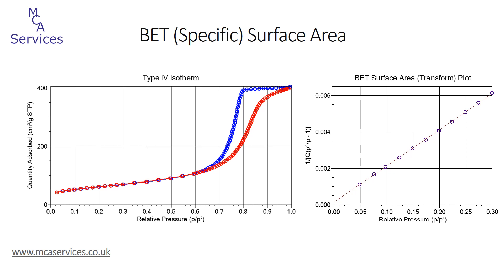There are several pieces of information that we can readily gain from this isotherm, and we're going to start by looking at the lower relative pressure portion of the adsorption isotherm. From this we can calculate the BET surface area of the material. We're going to cover this in much more detail in another video, but we can see the BET transform plot on the right, and the relative pressure range applied to it is 0.05 to 0.30. This provides a BET transform plot of excellent linearity and a positive intercept with the y-axis. The BET surface area for this particular sample is calculated to be 217 square meters per gram.